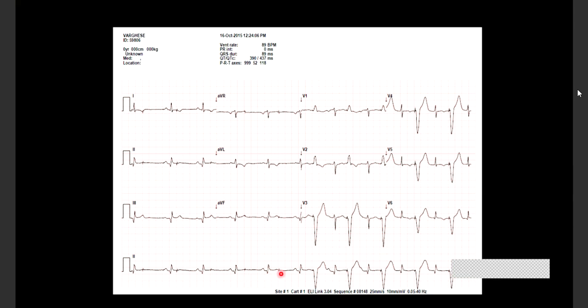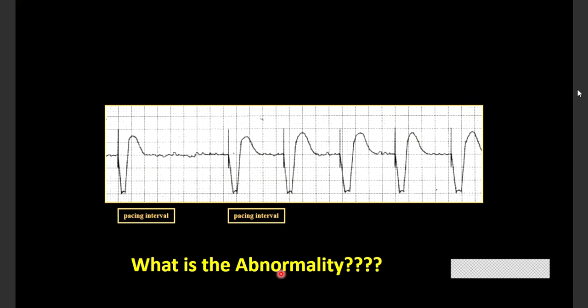Each pacemaker has its own magnet rate. Generally it's around 90, 98 or 99 or something like that when the battery is good. And when the battery drops, the magnet rate reduces to around 65, 75 or 70. It is different based on the pacemaker. So obviously, this is not a magnet rate. This is most likely an asynchronous mode which has been programmed in the pacemaker. This one is undersensing. As I told you, oversensing cannot be this. In oversensing, you will find that the pacemaker is not doing its job when it's supposed to. Okay, so what is the abnormality here?